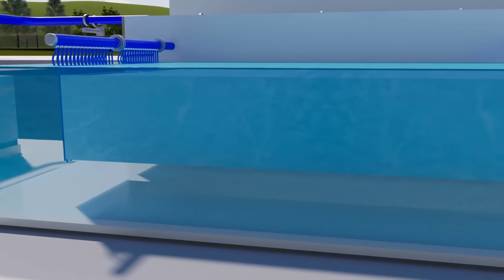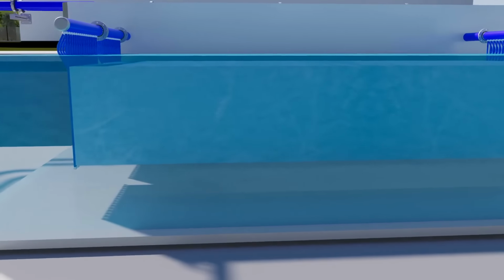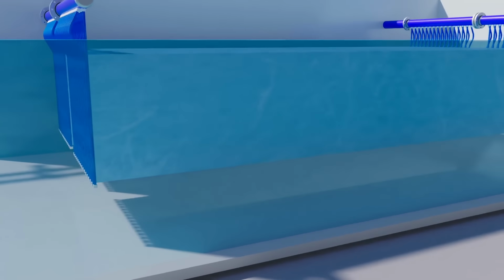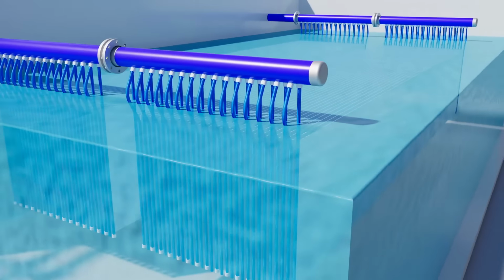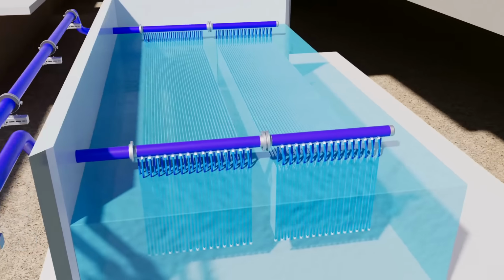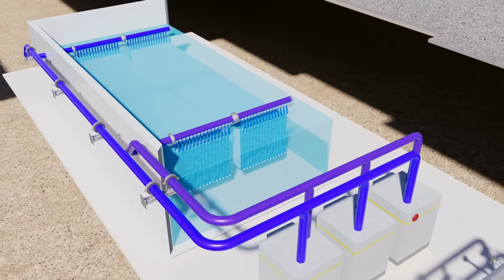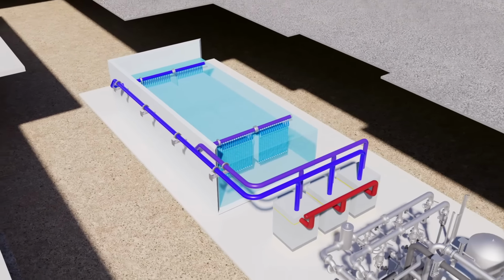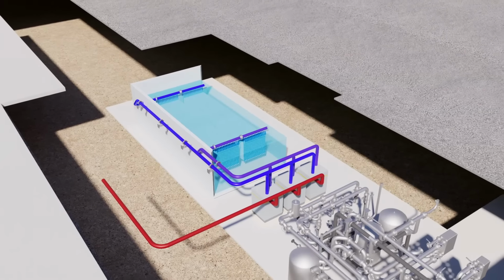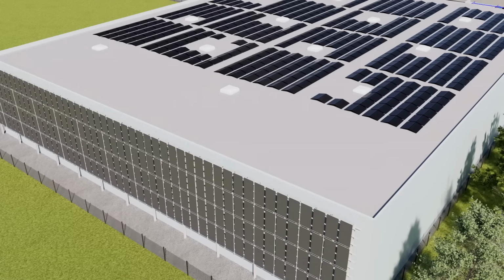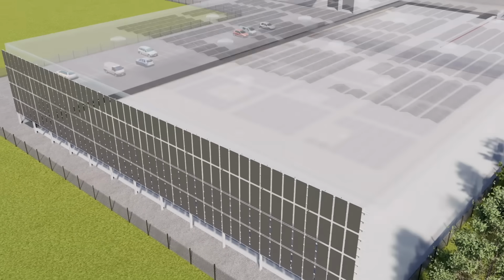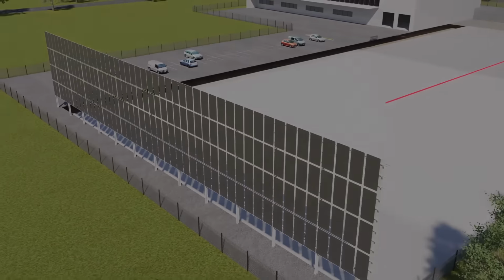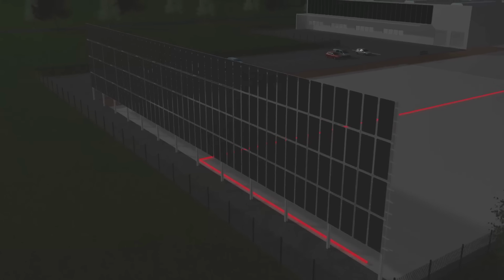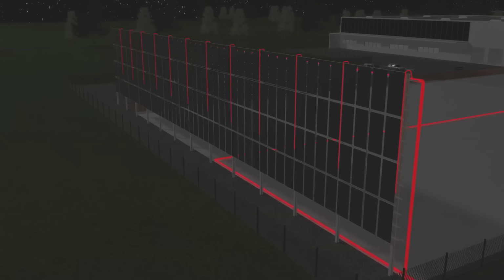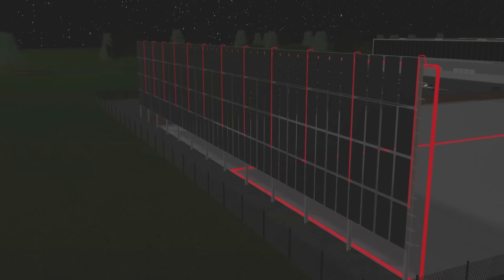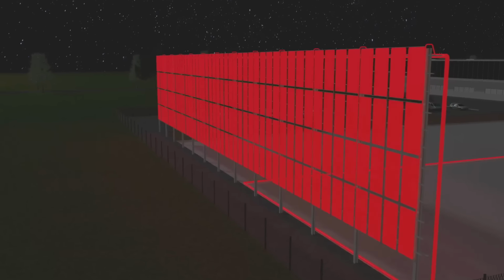In the summer, however, there is no need for heating and the ice melts. But that is when the machines and the server room need to be cooled. Therefore, the cold storage unit should not get warmer than 10 degrees Celsius. To prevent the storage tank from heating up, the water is cooled down again at night using heat pumps. The heat generated in this process flows to the air absorbers, which heat up to 30 degrees Celsius. The air absorbers release the heat into the cool night air.